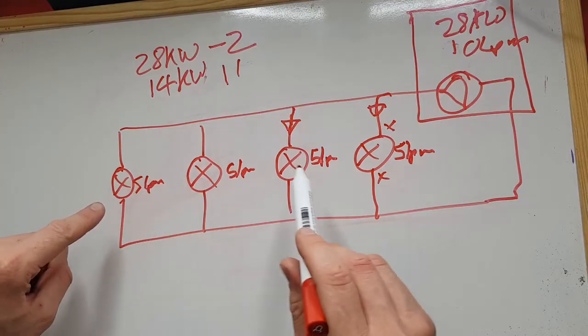In most of these valves, they have very small orifices, which actually gives them very high authority over the circuit. Valve authority is something we're going to cover in another video. But because they're pressure independent, they will keep balance throughout the varying boiler speed throughout the year.